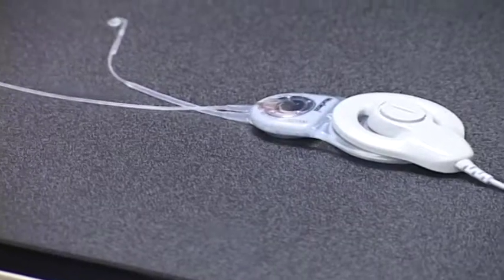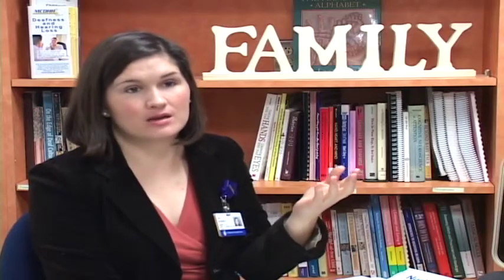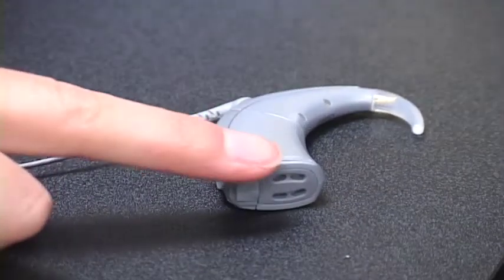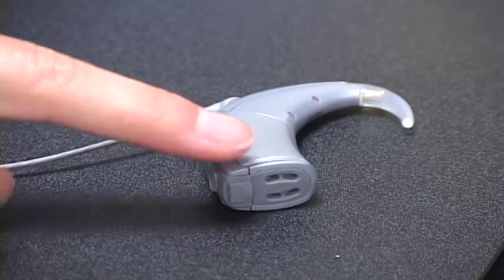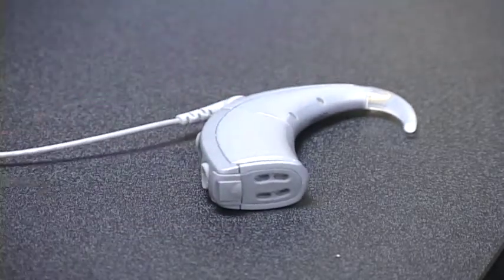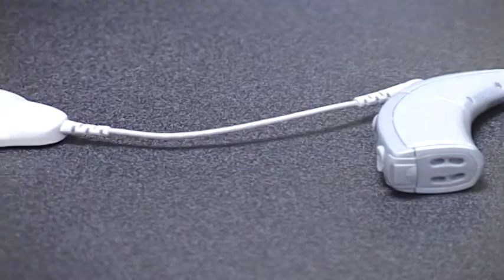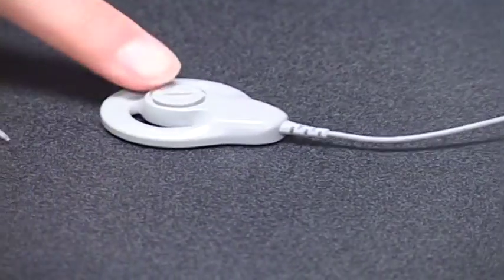Attached to the internal part are electrodes that are inserted into the cochlea, which is the hearing organ. Starting with the microphone, where sounds are picked up, at the bottom of the processor is a battery holder. Then we have the transmitting cable with the headpiece attached to it. Inside the headpiece is an antenna as well as a magnet.